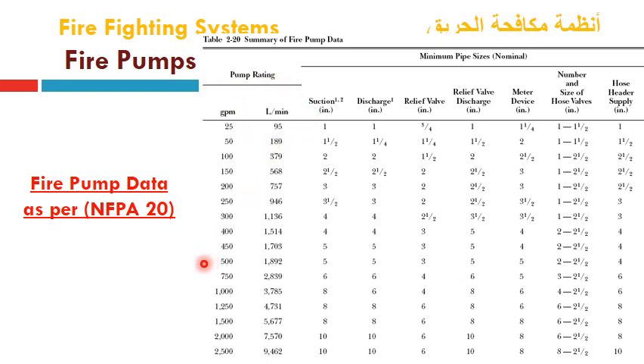So for example, if we have a 500 GPM pump, the suction line diameter should not be less than 5 inch, and the discharge line diameter should be not less than 5 inch, maybe 6, and the relief valve should be not less than 3 inch. The relief discharge valve of the pump discharge line is not less than 5, which is equivalent to the discharge line diameter. The meter device is also the same, and the number and size of hoses can be two, each of 2.5 inch.